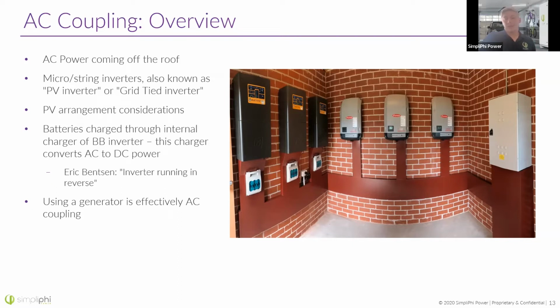Now, in this configuration, the battery bank would be charged through the inverter's internal charger. That's going to convert AC to DC. So normally, an inverter converts DC power or battery power to AC power to power the loads. In this case, when charging the battery, the inverter's charger is simply the inverter running in reverse. I've heard Eric Bentsen use this term in some of his trainings. If the inverter is working, the charger should work as well.